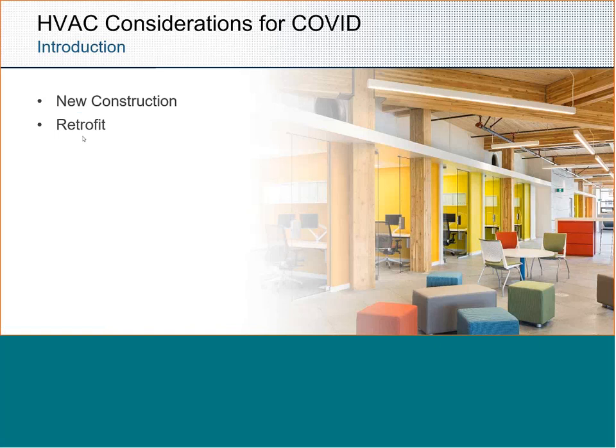Now, with retrofit, the one thing to always consider is introducing a higher MERV rating, upgrading units from MERV 8s to 13s or even up to HEPA. That obviously impacts the fan directly, as well as the static that the unit is seeing. Increasing the air changes is also going to impact the static of the system, and could even introduce having to rebalance the system if we're just bumping up the fan speed and supplying more air throughout the space.